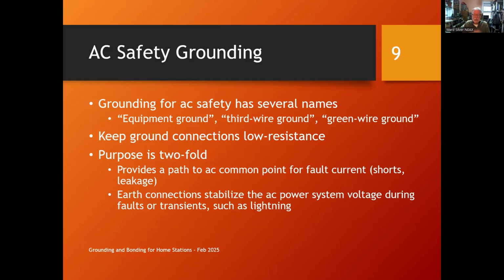and all of these earth connections, not only yours, but if you go out and you look at the power poles, almost all of them will have some big heavy ground wire coming down the pole. It could go to an actual ground rod, or it can be just wrapped around the bottom of the pole. It's called a butt wrap, and you put the pole in the hole, and that's how the ground wire connects to the earth.